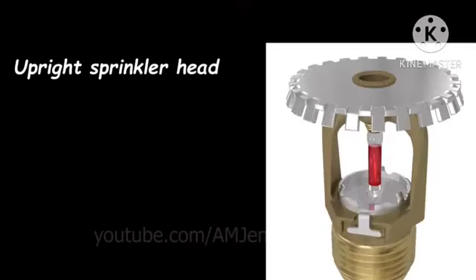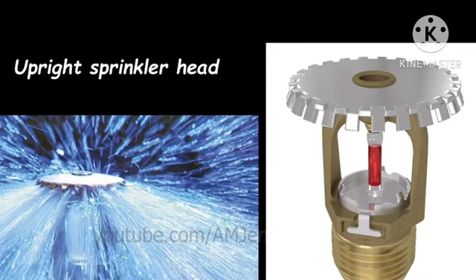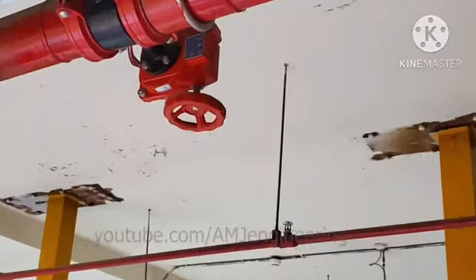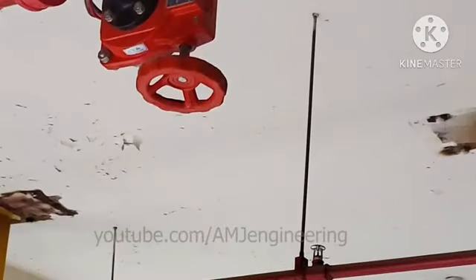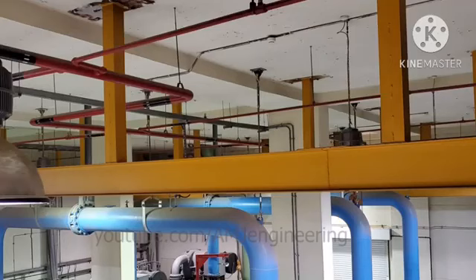Upright sprinkler head. Upright fire sprinklers spray water upward to a concave deflector, like an umbrella, producing a dome-shaped spray pattern. Rather than descending through the ceiling, these sprinkler heads are usually mounted on pipes just below the ceiling. Upright sprinkler heads are efficient at dispersing water between obstructions. Thus, they are frequently used for rooms that are inaccessible, such as mechanical rooms and in warehouses and industrial spaces. They are also often applied in structures with open ceilings.